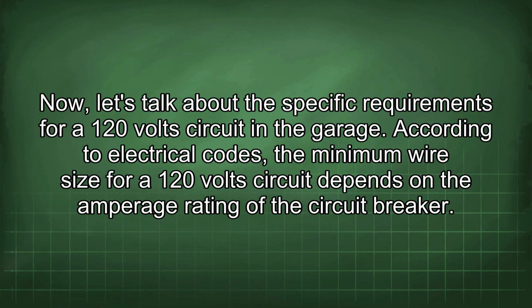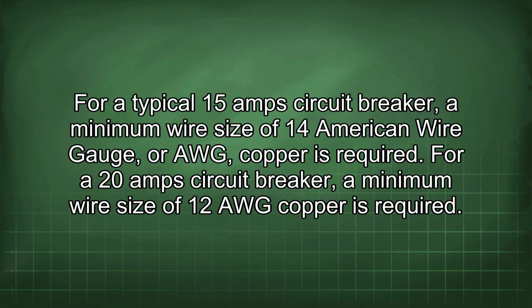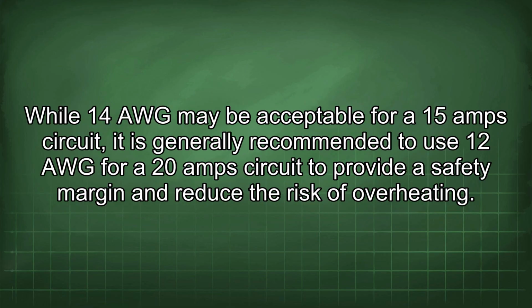Now let's talk about the specific requirements for a 120-volt circuit in the garage. According to electrical codes, the minimum wire size for a 120-volt circuit depends on the amperage rating of the circuit breaker. For a typical 15-amp circuit breaker, a minimum wire size of 14 American wire gauge, or AWG, copper is required. For a 20-amp circuit breaker, a minimum wire size of 12 AWG copper is required. While 14 AWG may be acceptable for a 15-amp circuit, it is generally recommended to use 12 AWG for a 20-amp circuit to provide a safety margin and reduce the risk of overheating.